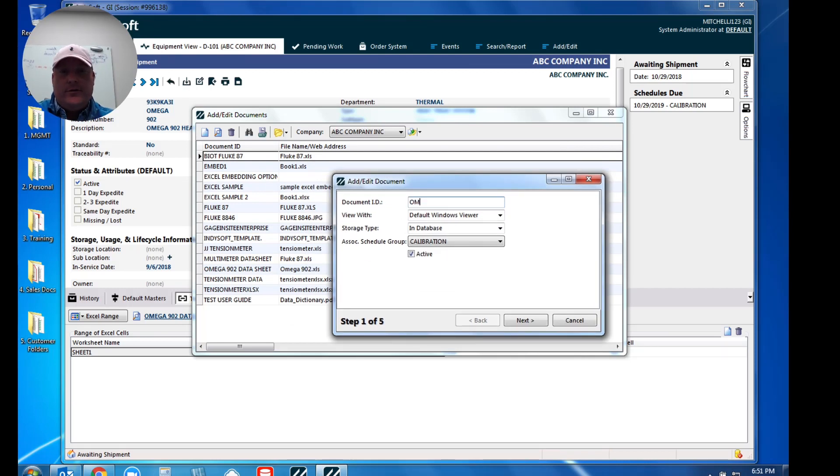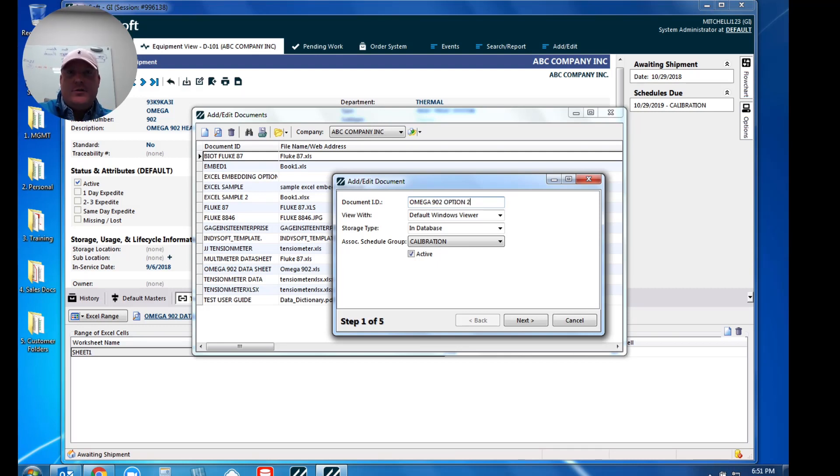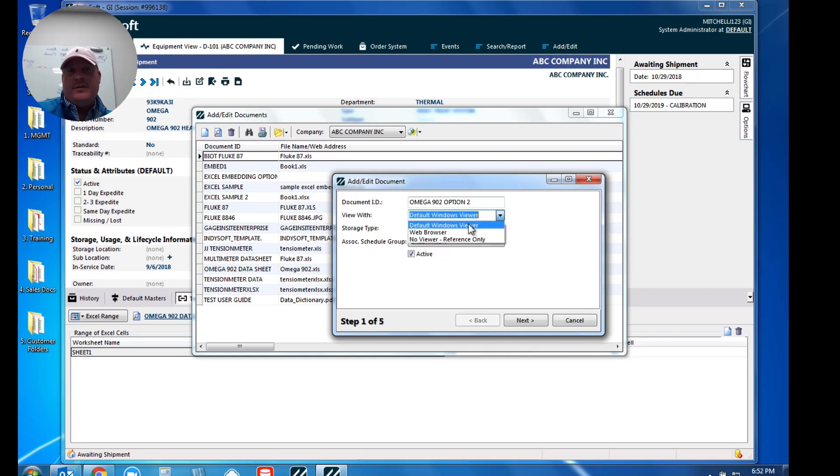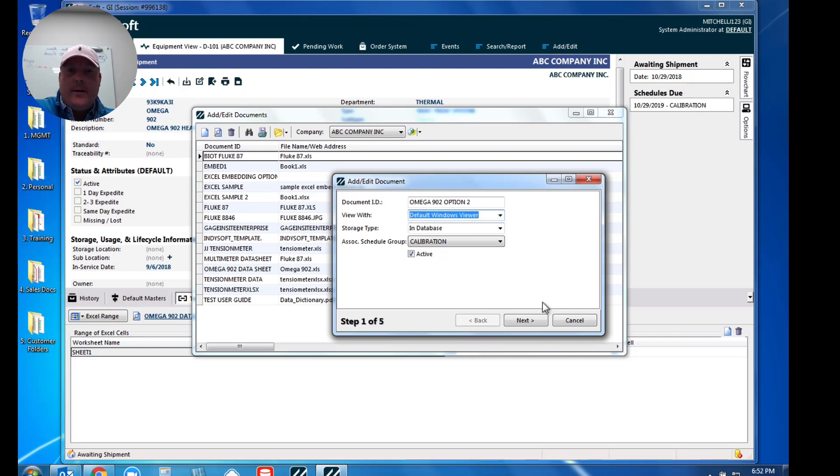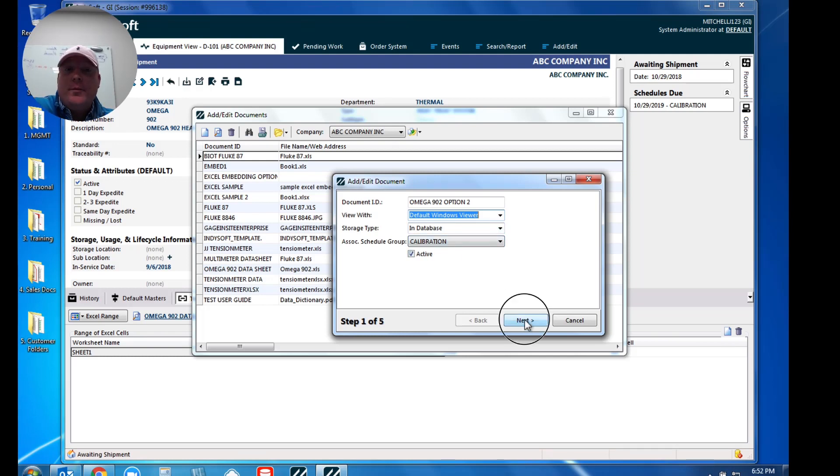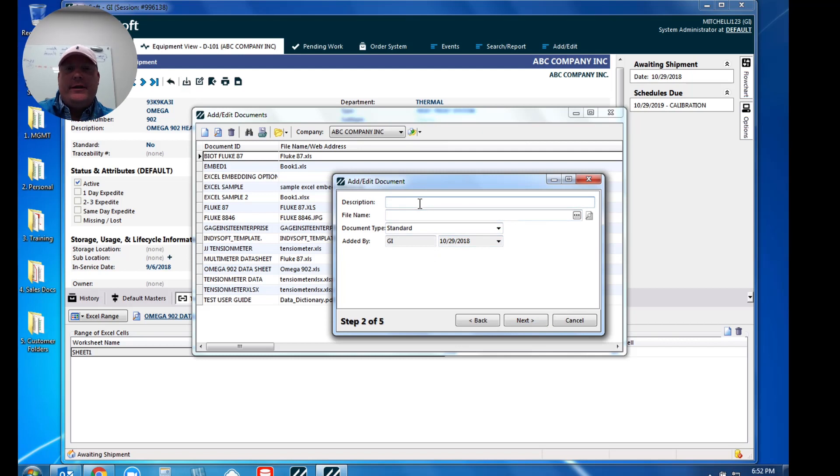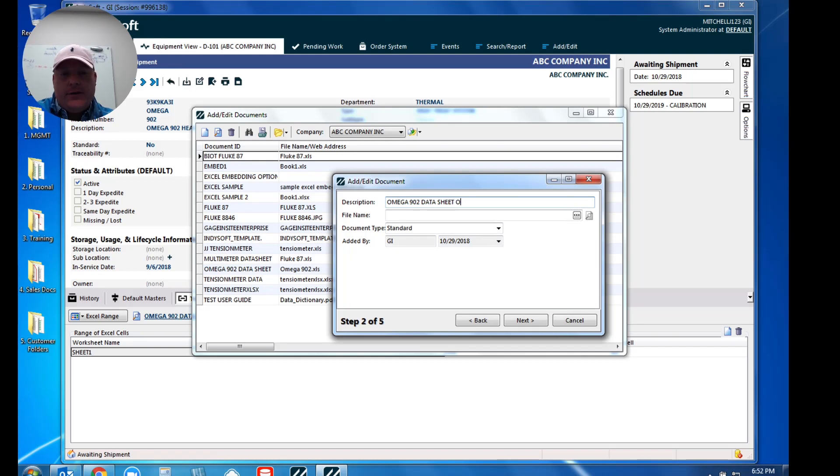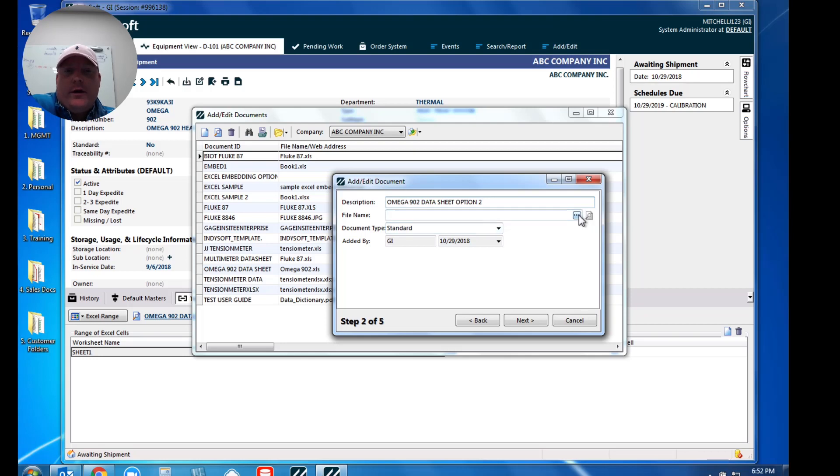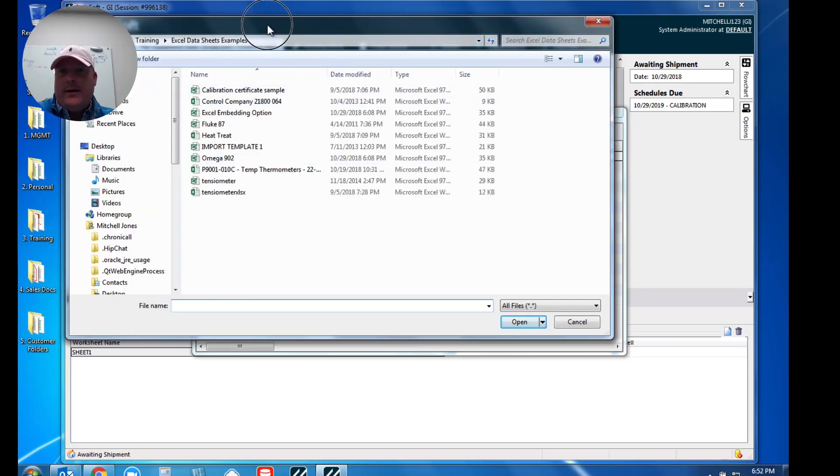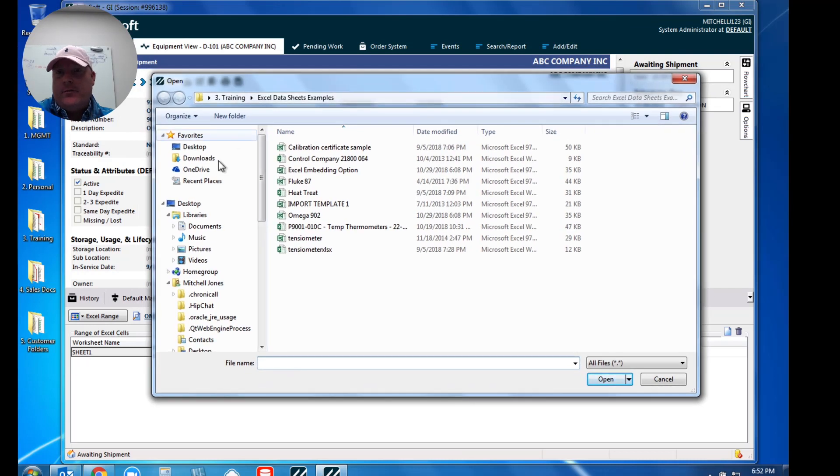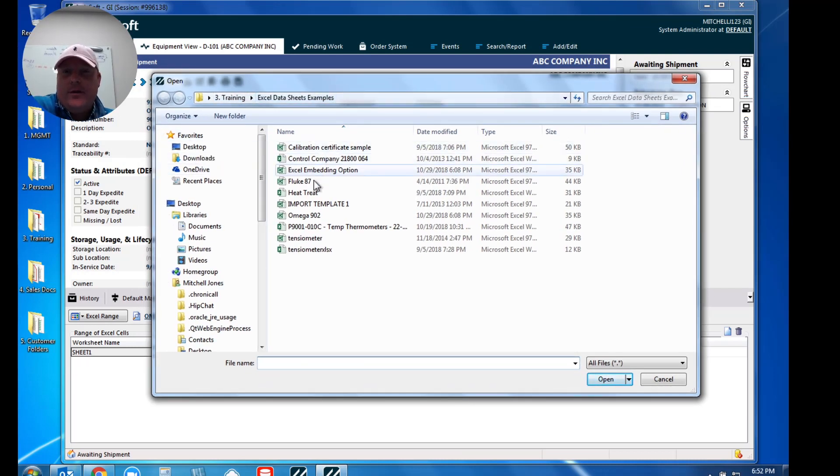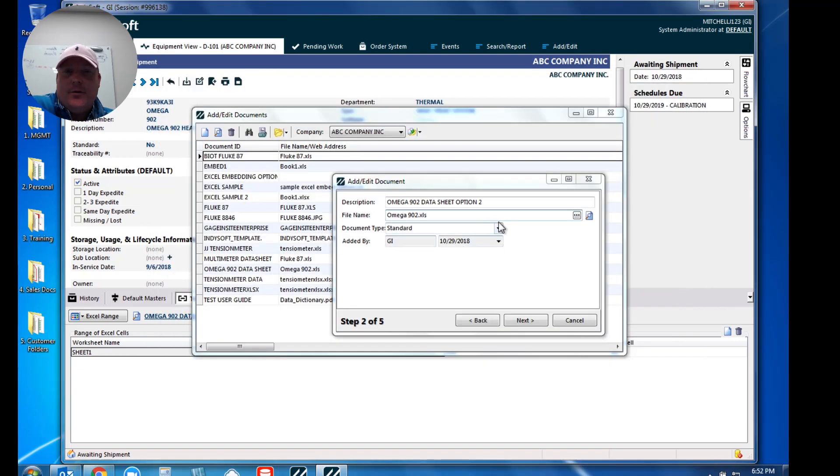Now you'll notice I already have my Omega 902 data sheet. So what I'm going to do is I'm just going to type in Omega 902 option two, just as a visual option for you to see. So we do want to use our default with Windows viewer option that simply says if it's an Excel file, the Windows application is going to open in Excel. I want a copy stored in my database. This is also tied to my calibration schedule group. But the next step is we're going to give this a description. So this is my Omega 902 data sheet. At this point we're going to navigate to the original source file. So on my network, and really just for me on my desktop, I've got a folder called Excel data sheet examples. So I'm going to grab a copy of that Omega 902.